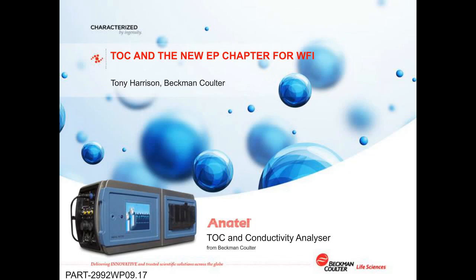A calibration adjustment, however, adjusts the analyzer measurement slope to give the best results when compared to certified TOC standards. And a 3-point calibration could also establish that the measurement slope is linear. And the PAT 700 automates both system suitability and calibration and calculates the pass-fail results and the linearity of the analyzer's measurement slope.